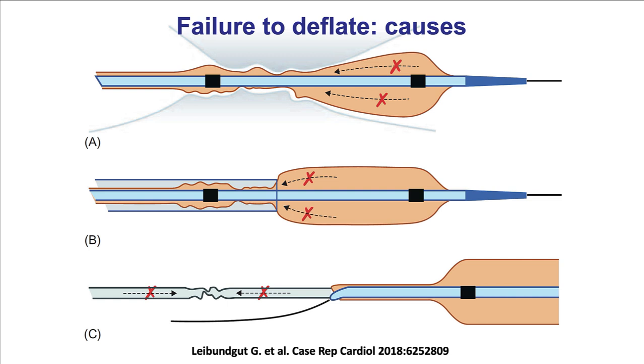There are several causes of failure to deflate. One is that the treated lesion is very tight and essentially strangulates the balloon, not allowing contrast to come back from the more distal portion. Another cause is premature withdrawal of the balloon into the guide catheter, which can strangulate the proximal portion and prevent deflation of the distal portion. Finally, damage or kinking of the balloon shaft can damage the hypotube that allows the saline and contrast mixture to return from the balloon.